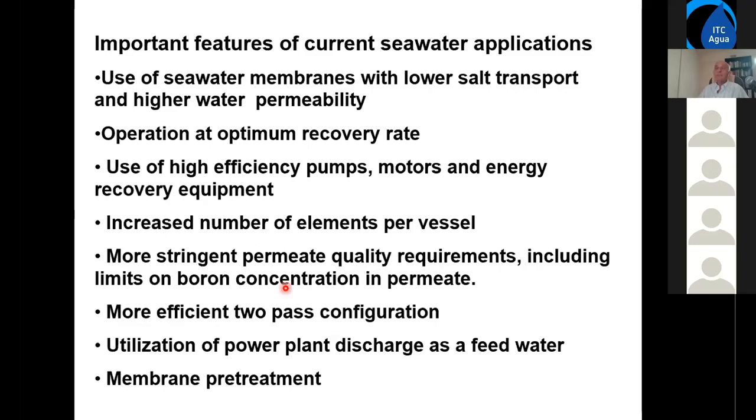Membrane pretreatment is a little controversial issue. We'll discuss this in this module soon. It removes all the colloidal matter, and there is water that has no colloidal matter. The problem is, one problem, it uses hypochlorite during the backwash process, and this has to be flushed out so as not to reach the membrane, but also this hypochlorite breaks down organics, and some organics end up in RO. So in the end, this membrane pretreatment could result in biofouling in the RO process. So this is something which is not completely resolved.